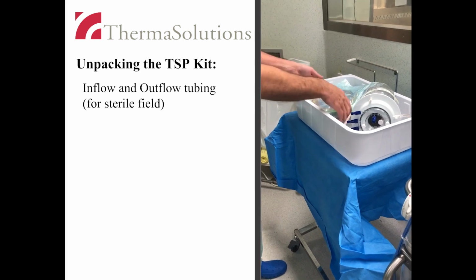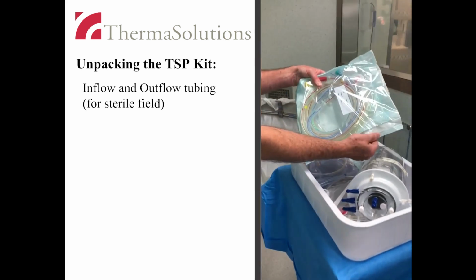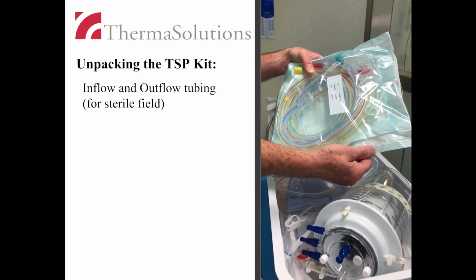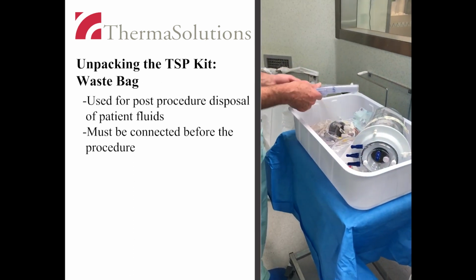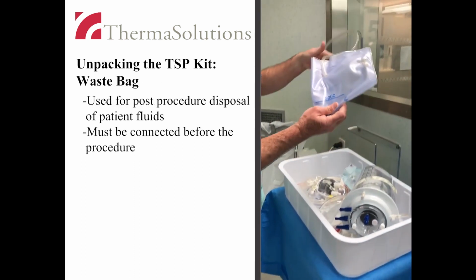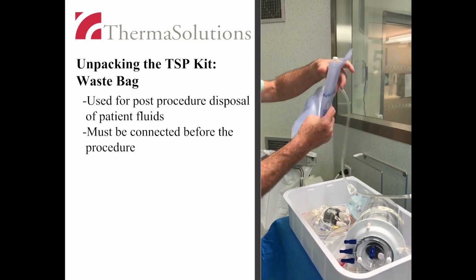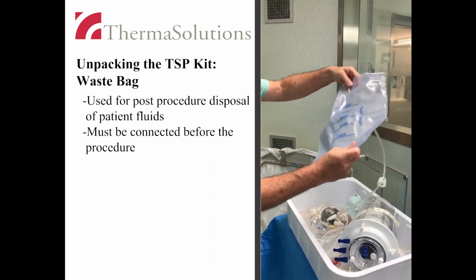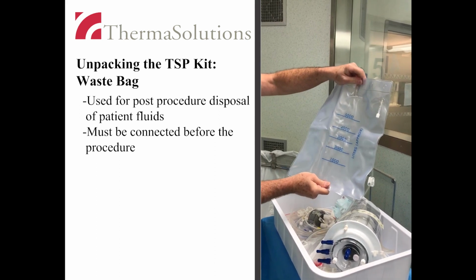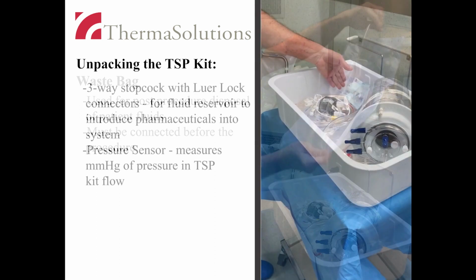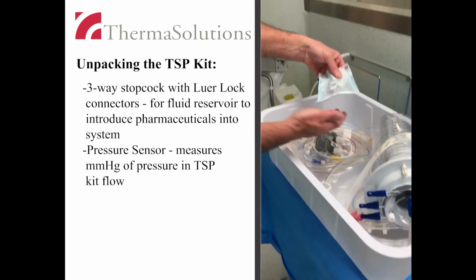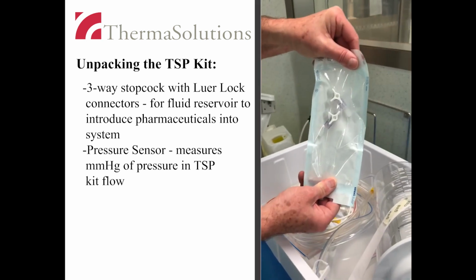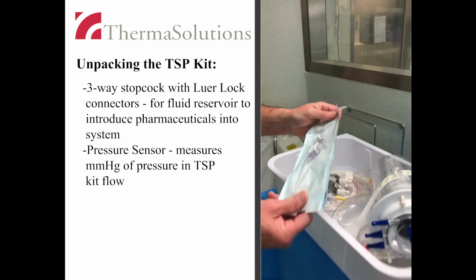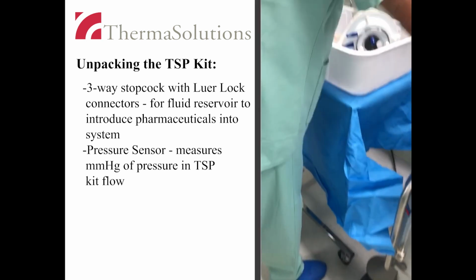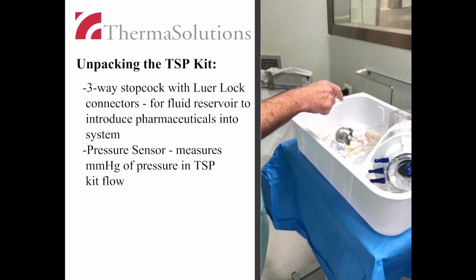Inflow and outflow tubing and temperature probes are individually packaged for use in the sterile field. The waste bag is used for disposal of the patient fluids once the case has been completed. The waste bag should be connected to the procedure kit system during setup. The three-way stopcock with luer lock connectors will be attached to the top of the fluid reservoir and will be used to introduce pharmaceuticals into the system during the case.